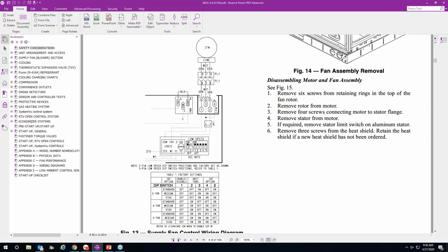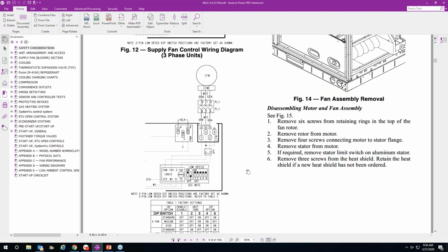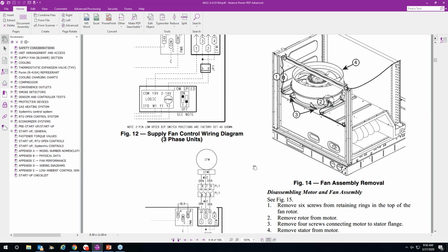And again, all these dip switches can play into it, as well as your ABC slide switch and your potentiometer. So exercise all those if we're not getting that signal back to the motor. Okay, so that's the troubleshooting of it. Pretty simple. And those are all the things that can cause your limit trip issues and motor operation issues.